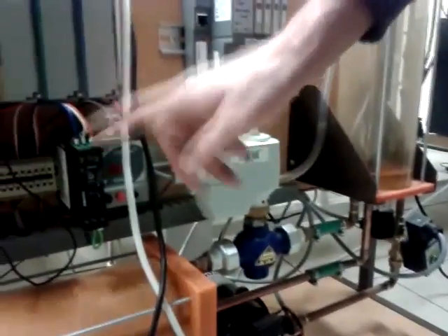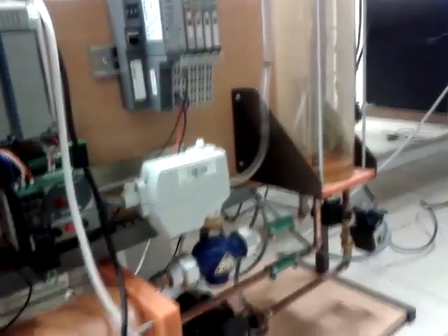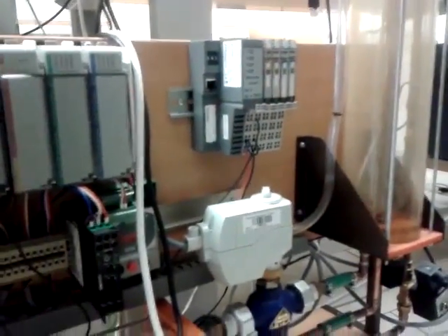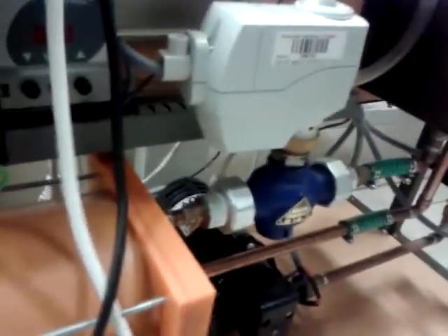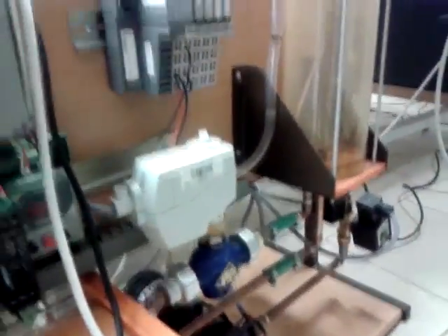That means it must be converted to voltage using this frequency to voltage converter, and the flow is controlled by this proportional valve. That means this solenoid valve, but not a standard on-off, but a proportionally controlled solenoid valve. That means it is then used as cascade control. This flow rate loop is the slave loop. This is the master loop.